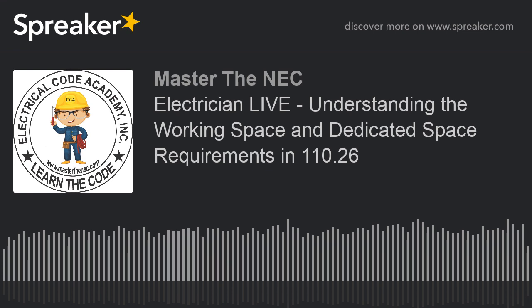110.26. What does it say? What is it talking about? It says access and working space shall be provided. So it shall be. It's not an option. It shall be provided, and it has to be maintained about all electrical equipment to permit ready and safe operation and maintenance of such equipment. Okay, so in this, we're going to have a subdivision. We're going to have an A, a B, a C, and we're going to even have a D and an E that we have to worry about. In fact, we even have an F, but we're not going to talk about that today.